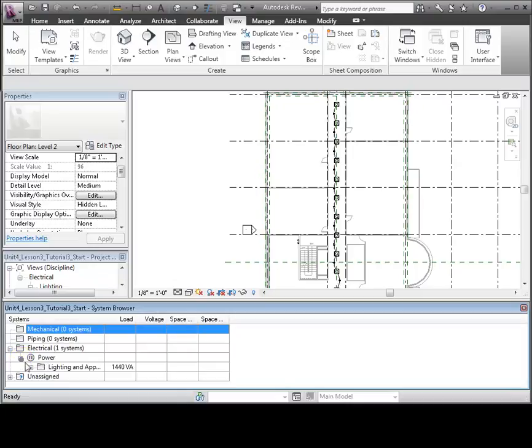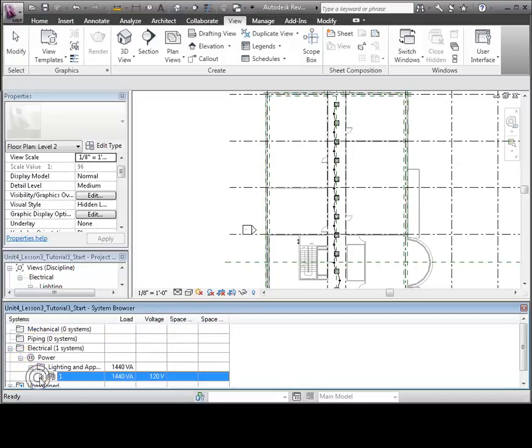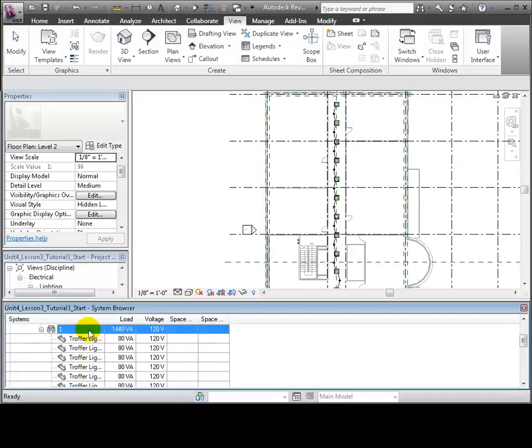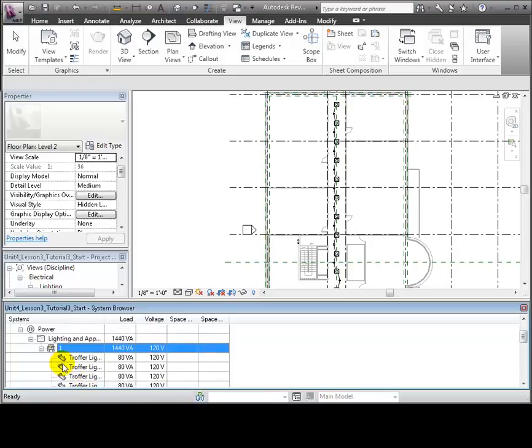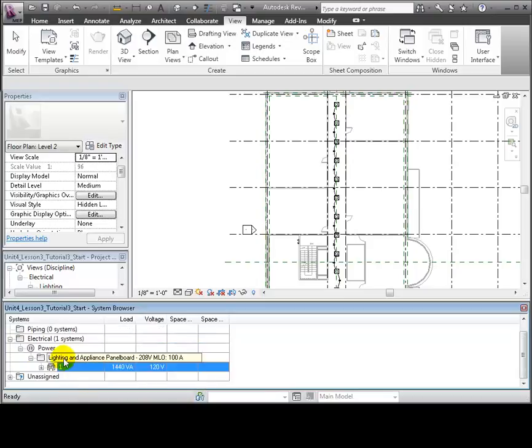You can expand the Electrical, then Power section, and you'll see the Lighting and Appliance panel boards placed in the project and the circuits assigned to each panel. Each circuit shows all of the fixtures assigned to that circuit and the total load created by the fixtures in the circuit. This entry in the System Browser corresponds to the panel that we placed on Level 2 and the circuit for the corridor lighting fixtures.